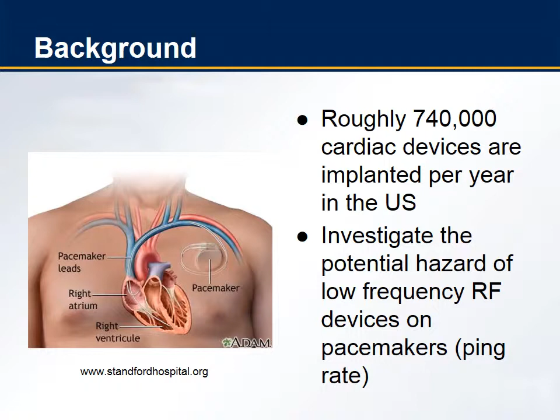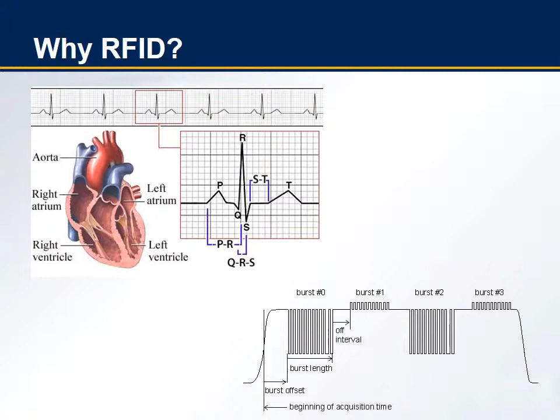Here we have the EKG from a heart shown in the upper portion. In the lower portion we have the ping rate. As you can see, the ping rate is going to have a short burst and then a low, and then another short burst and then a low. And this is a problem with demand type pacemakers, and all that means is that the pacemaker is going to be active when it senses no heartbeat, and it will shut off when it senses a heartbeat. So in the worst case scenario, the pacemaker sees that ping rate, interprets it as a heartbeat, and then shuts off.